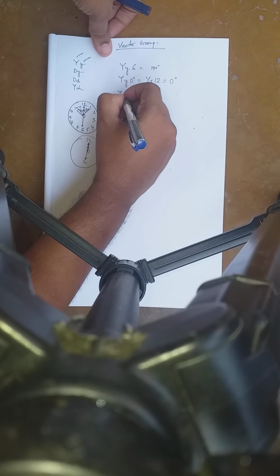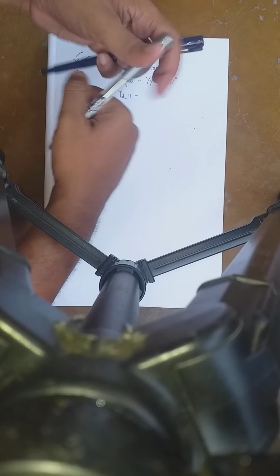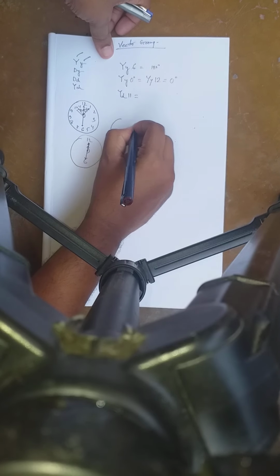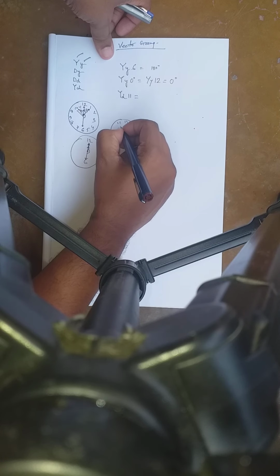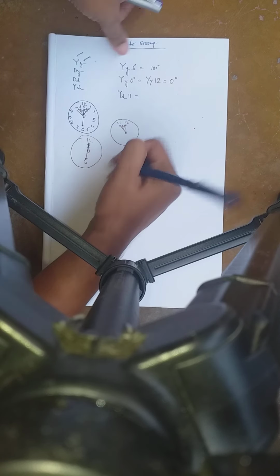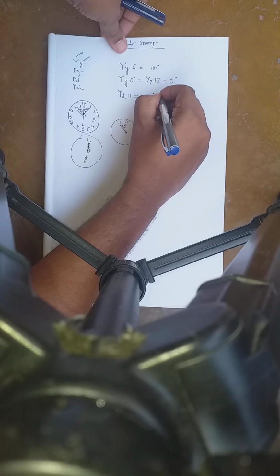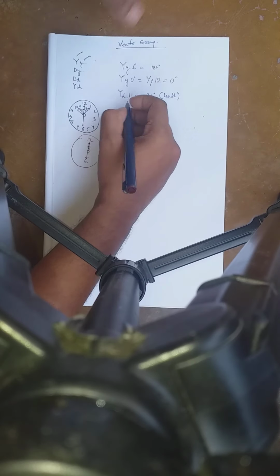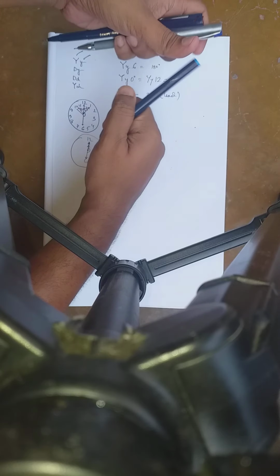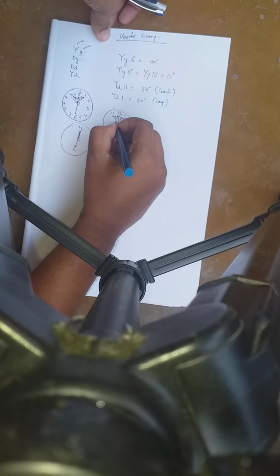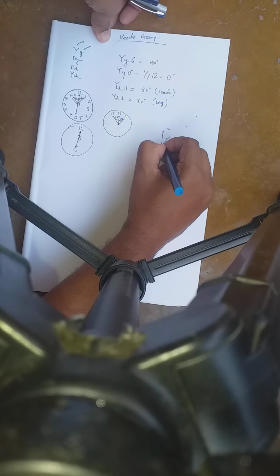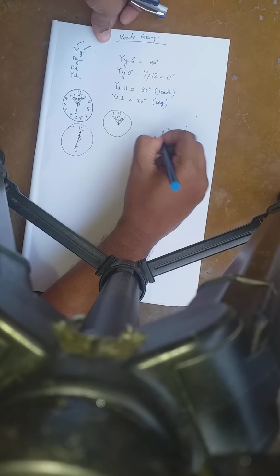Suppose I write Yd11. This is 12, this is 11, and this is 30 degrees lead. I am explaining why lead and why lag. Suppose Yd1, that means 30 degrees, which is also 30 degrees but lag. This is 12, this is 1, and this is 11.